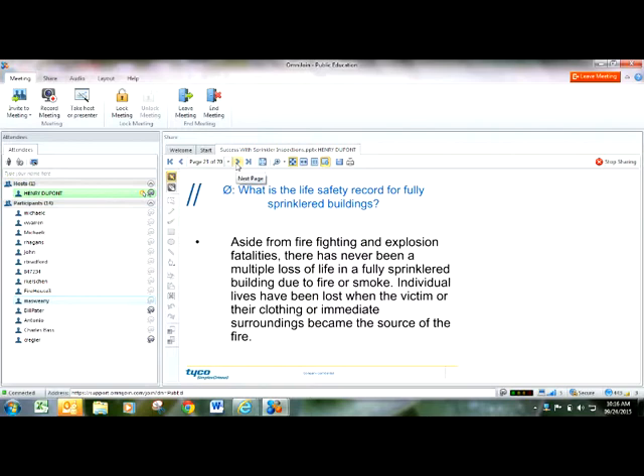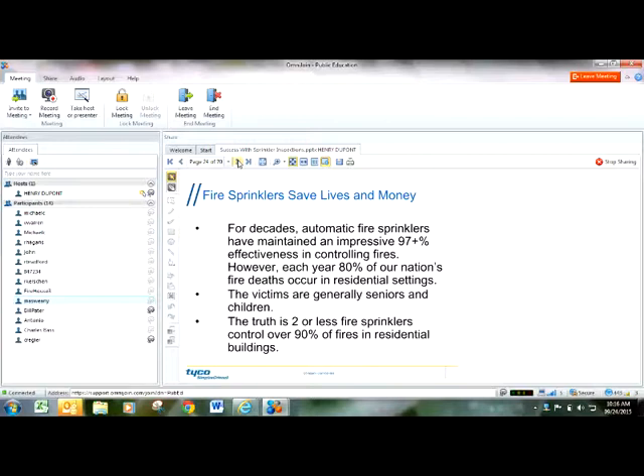What is the life safety record for a fully sprinklered building? And I might add, not just fully sprinklered, but properly maintained. Aside from firefighters and explosions, there hasn't been a multiple loss of life recorded for a fully sprinklered building that is maintained correctly. For decades, sprinklers have maintained an impressive 97% effectiveness in controlling fires. Most of our nation's deaths each year are elderly and young in unsprinklered buildings. And generally 2 or fewer sprinkler heads can control over 90% of fires.